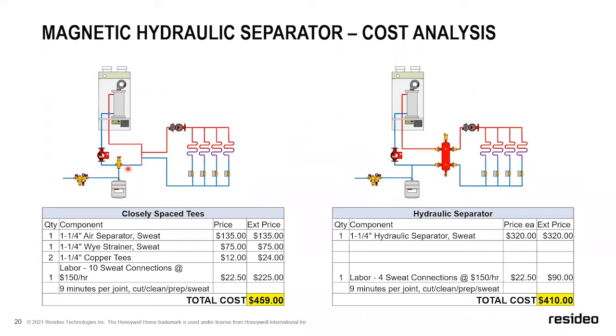In this system, a very common system you'll see in virtually every modulating boiler manual, you're going to have an air eliminator and a set of closely spaced tees to give you a form of hydraulic separation. This way, with the same examples I was showing you earlier, 10 gallons a minute or 2 gallons a minute, you're keeping that flow consistent here. There are a couple of things you need to take into account: look at the number of fittings and the number of joints you have to make. We've got 2 sets of tees here, so 1, 2, 3, 4, 5, 6 1.25-inch connections right here. Our air eliminator has 2 more, so now we're up to 8.